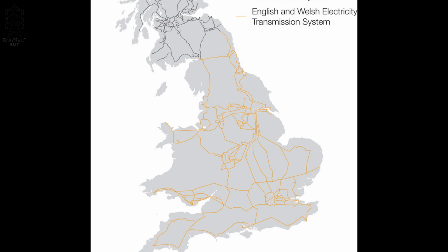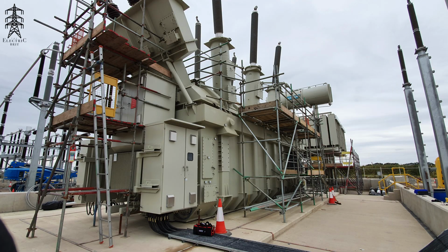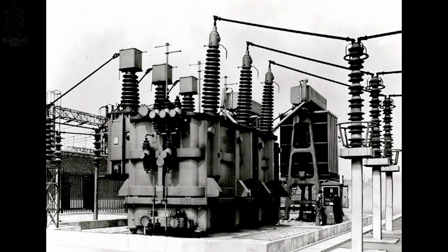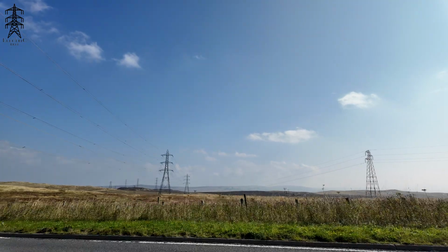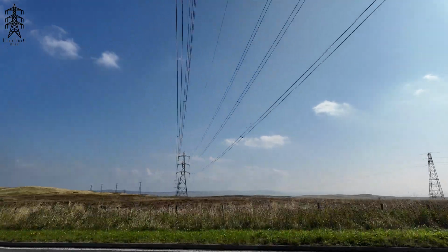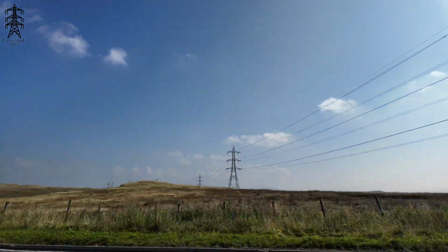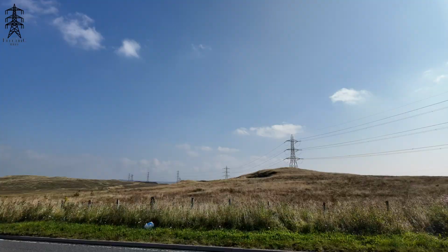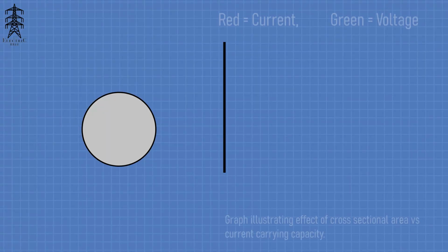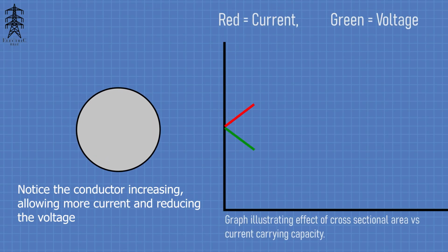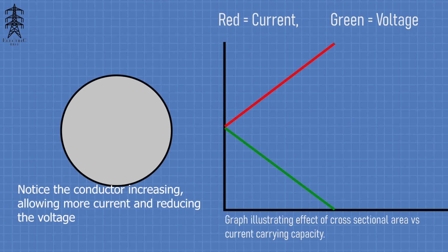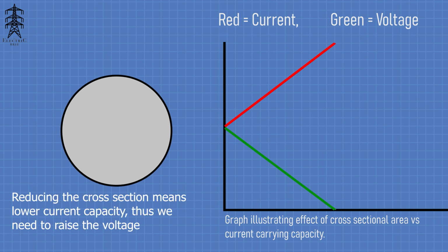High voltage transformers in the UK that operate at 132, 275 and 400 kV, which are the transmission voltages, are called supergrid transformers, or SGTs. Transformers are devices used for changing voltage because higher voltages are more efficient at being transported longer distances, because of Ohm's law. Increasing the voltage means a decrease in current, meaning we can have thinner conductors in our cables and overhead lines.